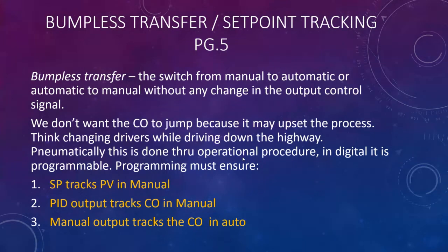So when you flip the knob, you're not going to get a big rush of air going out to a valve and opening a valve, or losing your air and closing the valve. Basically, you're balancing what's currently happening in the operating process with what you want it to be when you switch it into manual or automatic. So pneumatically, it's done through operational procedures, some kind of hand work that you have to do.